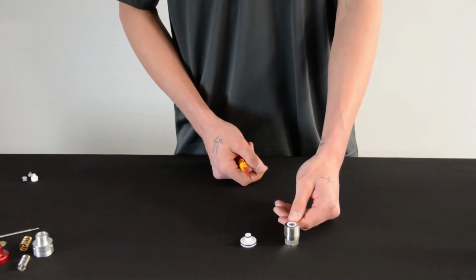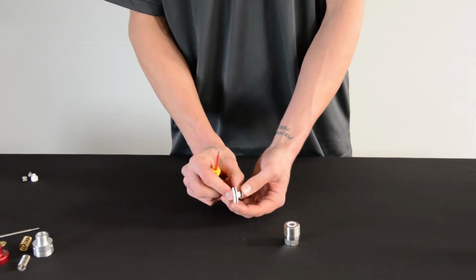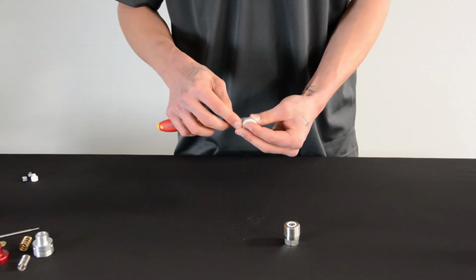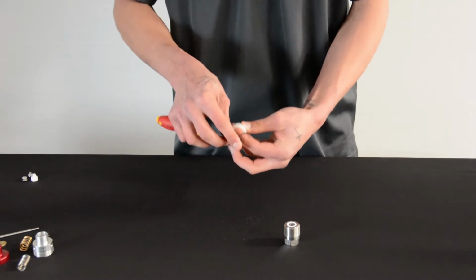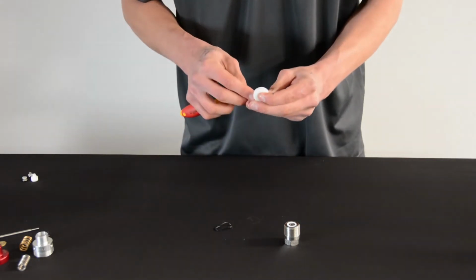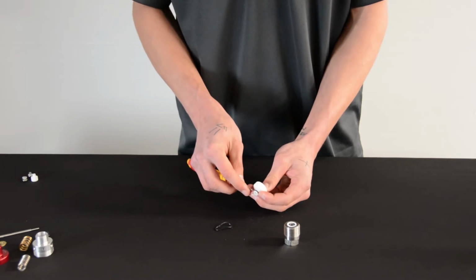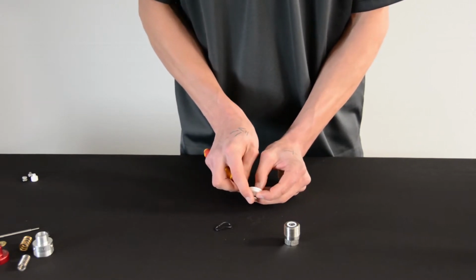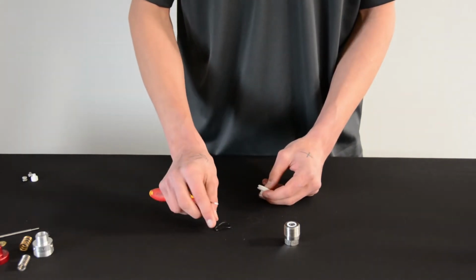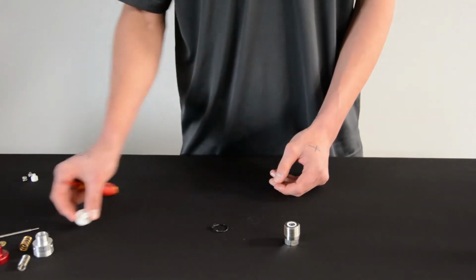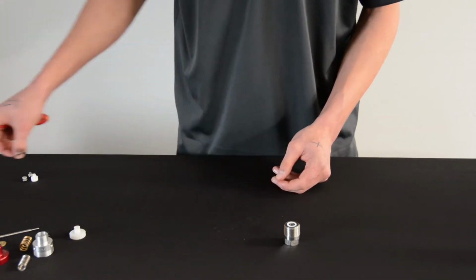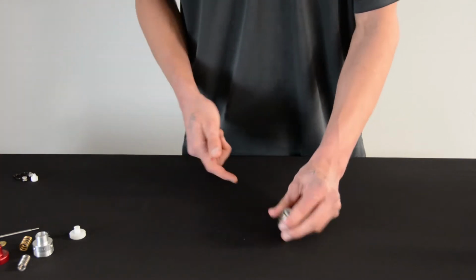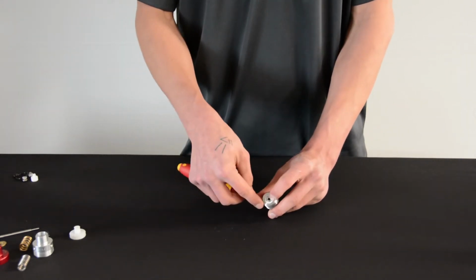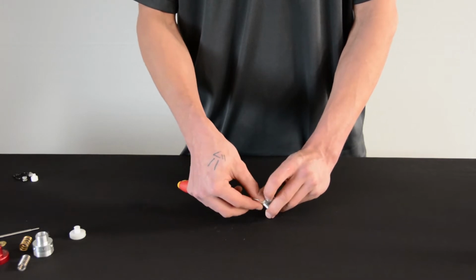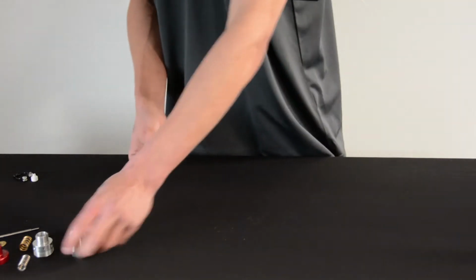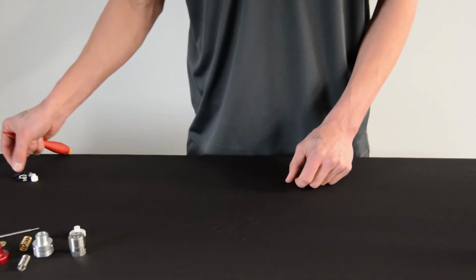There's a Teflon O-ring on the valve body and 2 Buna O-rings on the piston. Take a small screwdriver and remove the O-rings from the piston. You want to keep your piston, but the 2 Buna O-rings can be discarded. Then, using your small screwdriver, remove the Teflon O-ring from the valve body. Keep the valve body, but you can discard the Teflon O-ring.